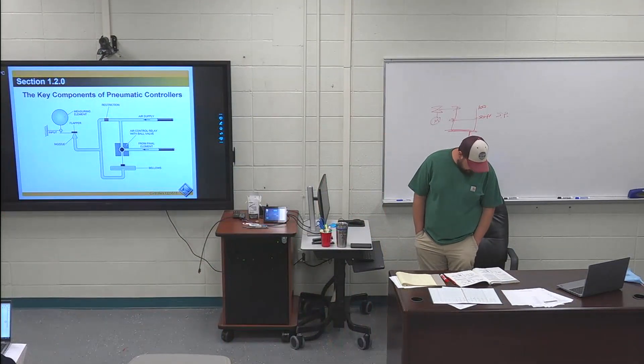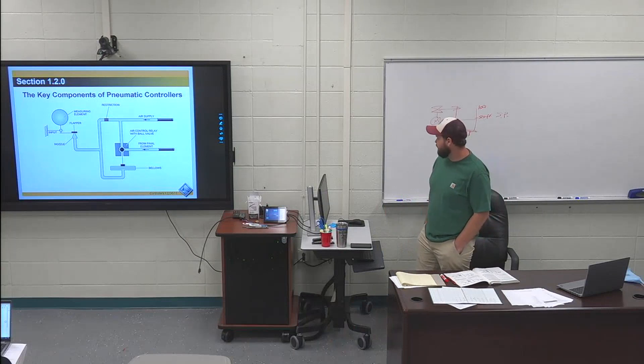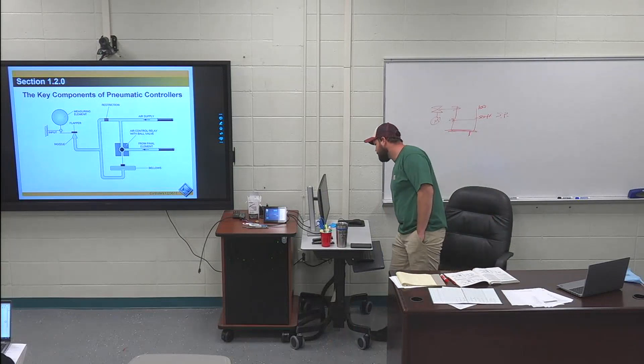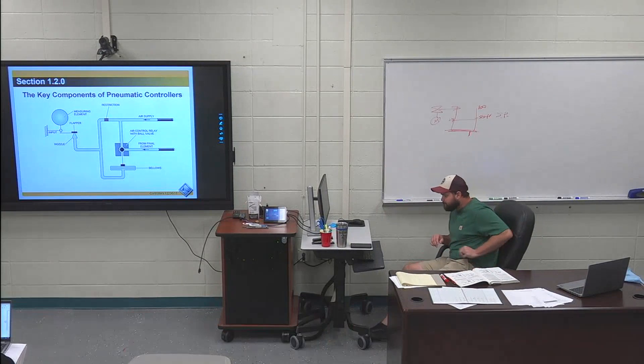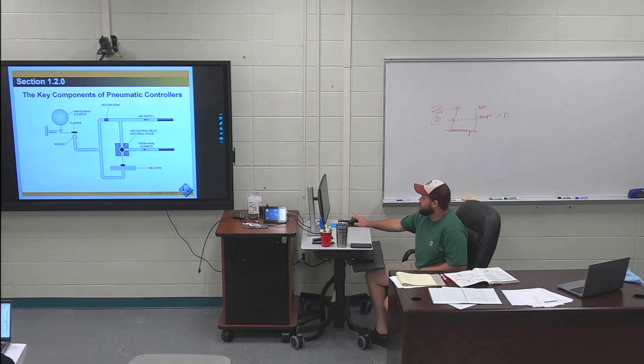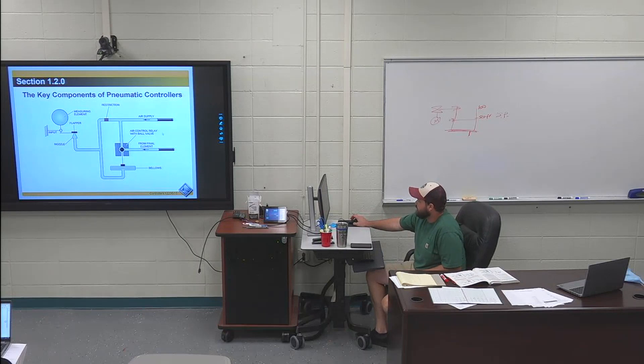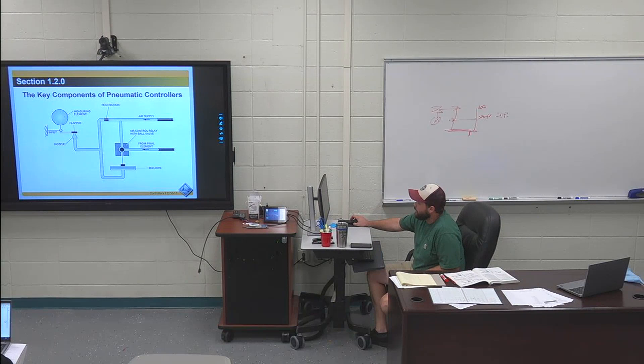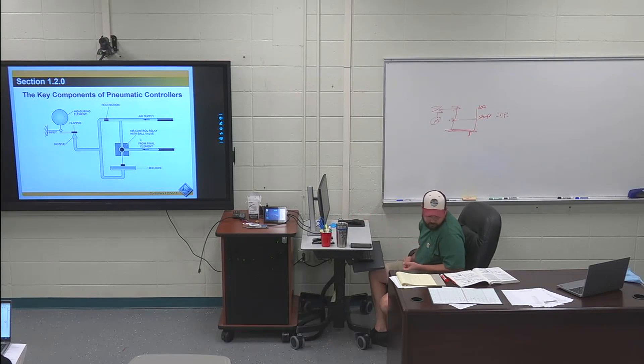Pneumatic controllers — I'm not going to go into the breakdown of these too much because the text covers the internal parts and how they work, including bellows and air supply. It's good to know, but if something in a pneumatic controller went bad, you're replacing the whole controller. You're not going in to replace certain parts — you change the whole controller.